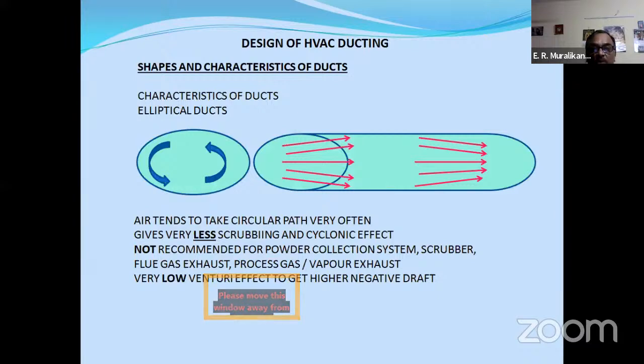Now, elliptical ducts. Air tends to take a circular path very often but gives very little scrubbing and cyclonic effect, because to get a cyclonic effect there should be proper radial flow and high centrifugal force, which does not happen in elliptical ducts. Not recommended for powder collecting systems, scrubbers, flue gas exhaust, process gas, vapor exhaust. So these will not be applicable for elliptical ducts.